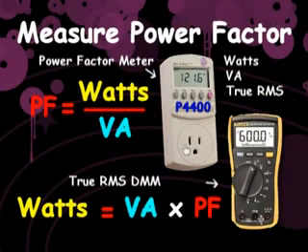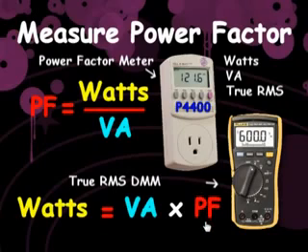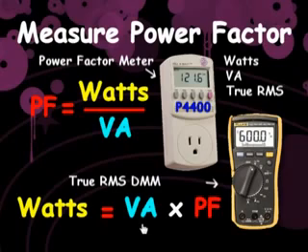This power factor meter also measures watts, VA, and true RMS current and voltage. If the device manufacturer specifies the power factor, you can calculate watts by using a digital multimeter to measure the volt-amps, and then multiplying that times the power factor.